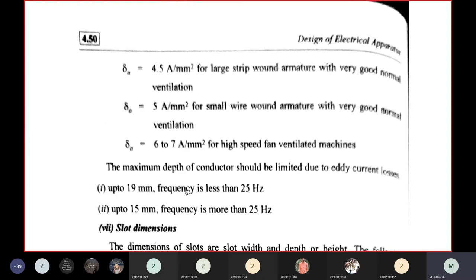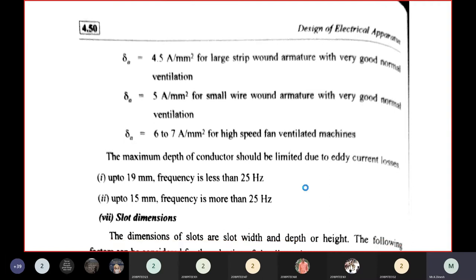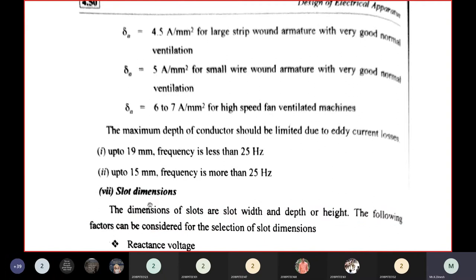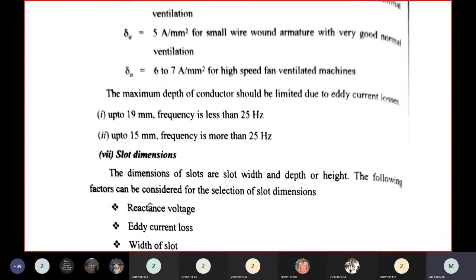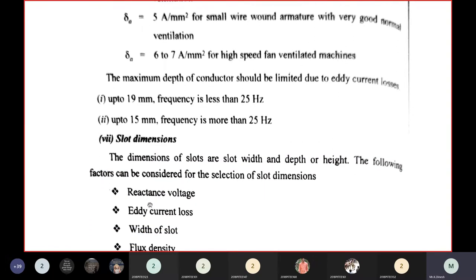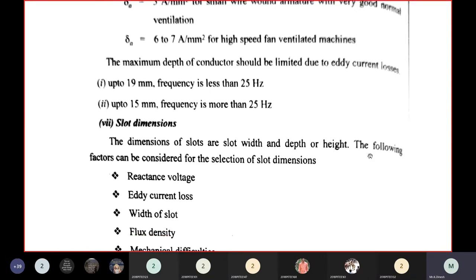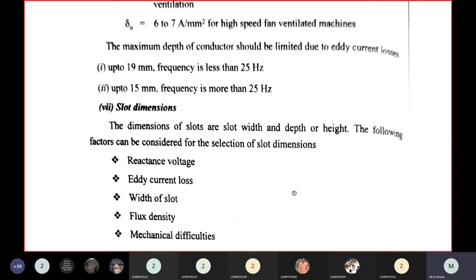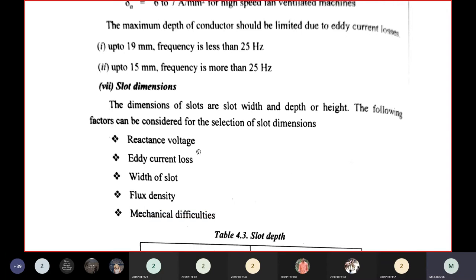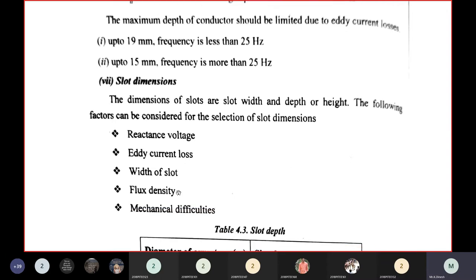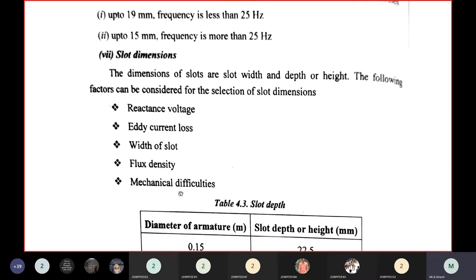Conductor depth: up to 19 mm for frequencies less than 25 Hz to avoid eddy current losses; up to 15 mm for frequencies above 25 Hz. Slot dimensions depend on width and depth or height. Factors to consider for slot dimensions include reactance voltage, eddy current loss, width of slot, flux density, and mechanical difficulties.